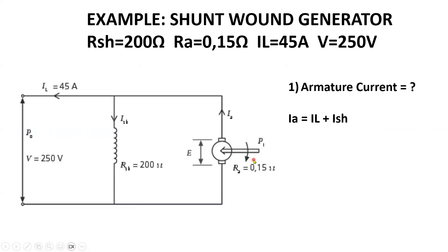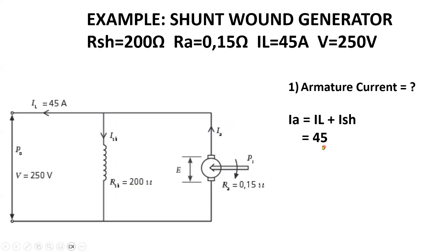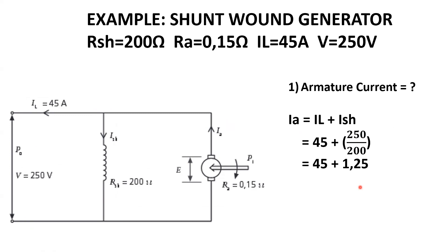In this example we have a shunt-wound generator with a shunt resistance of 200 ohms, an armature resistance of 0.15 ohms, a supply current to the load of 45 amps, and a terminal voltage of 250 volts. To calculate the armature current, IA equals IL plus I-shunt. The shunt current is the terminal voltage of 250 volts divided by the shunt resistance of 200 ohms. Note that the terminal voltage equals the voltage across the field winding since they are in parallel. Therefore the armature current is 45 plus 1.25, giving 46.25 amps.